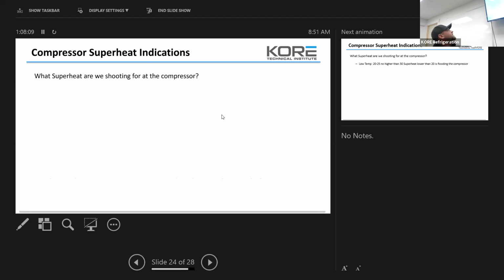Compressor superheat indications. What superheats are we shooting for on the compressor? Here are your ranges, guys. And I always say no lower than 20 on anything, because that's when you're really coming back hard, especially on single systems. So low temp, 20 to 25, no higher than 30. Lower than 20 is flooding the compressor.